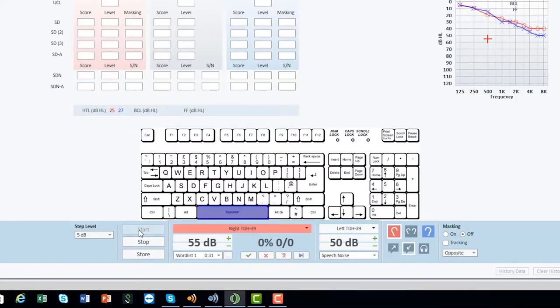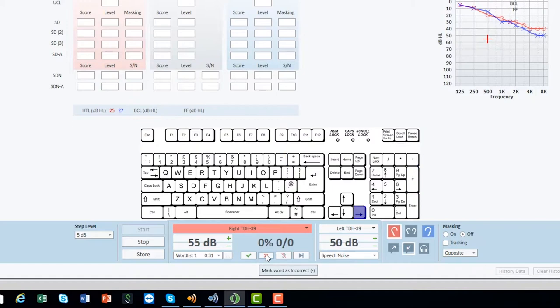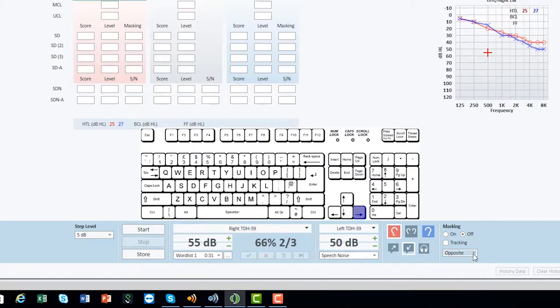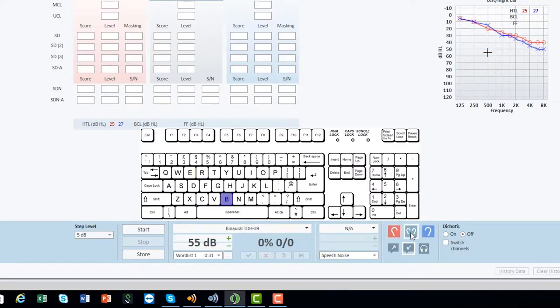Start measurement using spacebar, scoring of words plus or minus, or to skip the word use the right arrow. To activate or deactivate masking use M, left L or right R, binaural B, dichotic B plus D. In the binaural mode, dichotic testing is available if the speech material supports this.